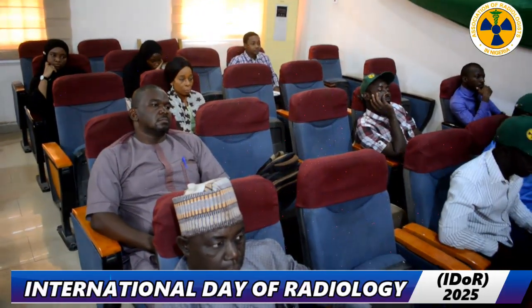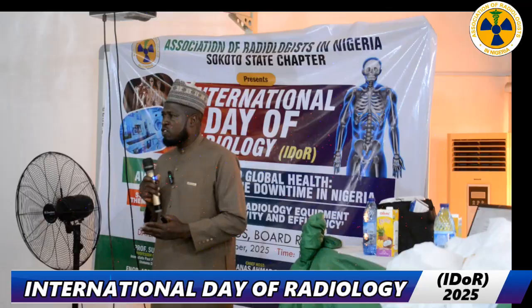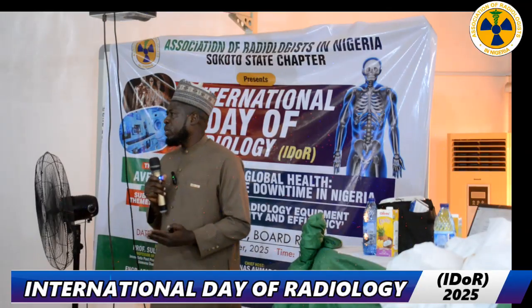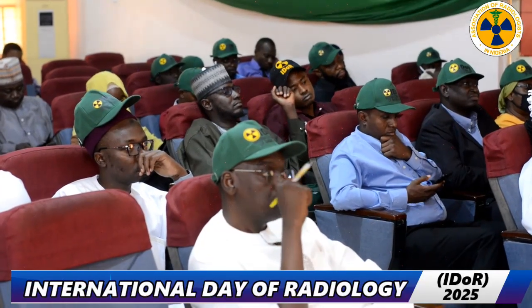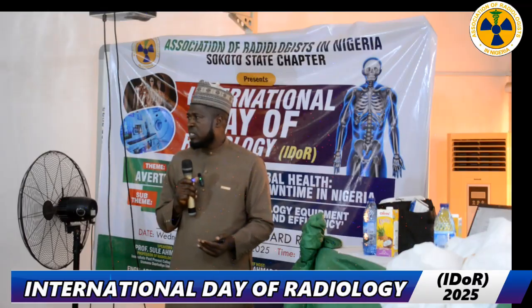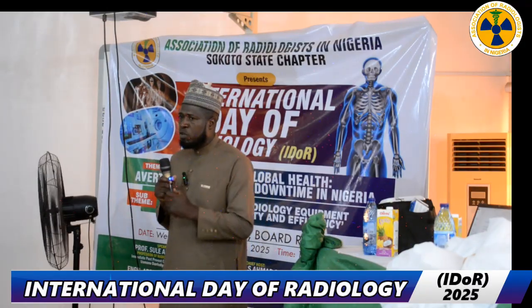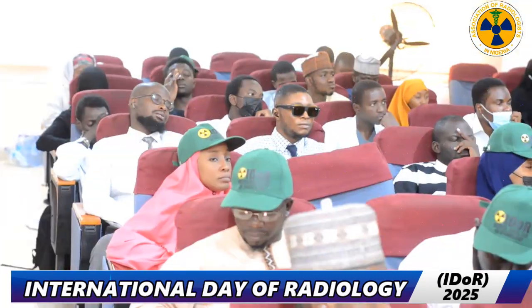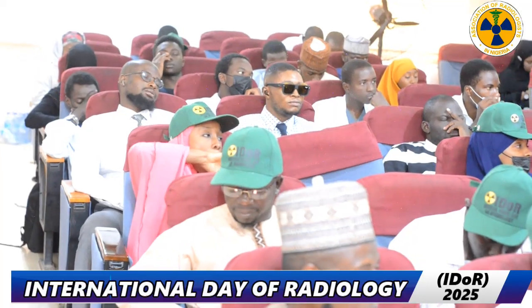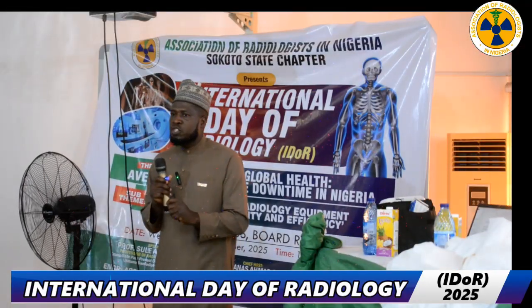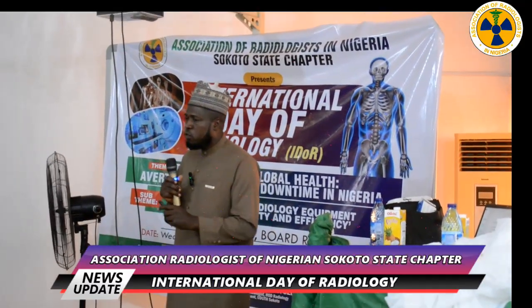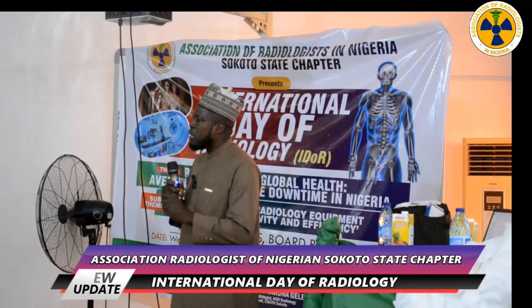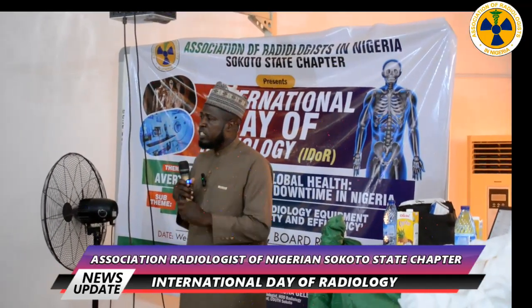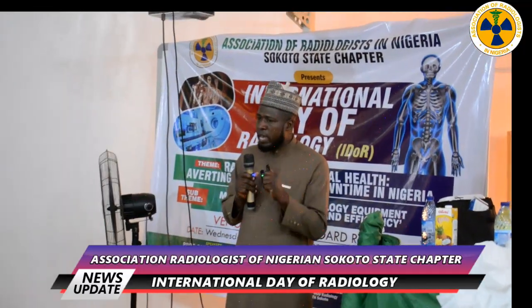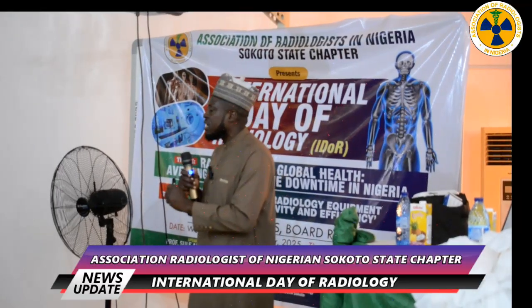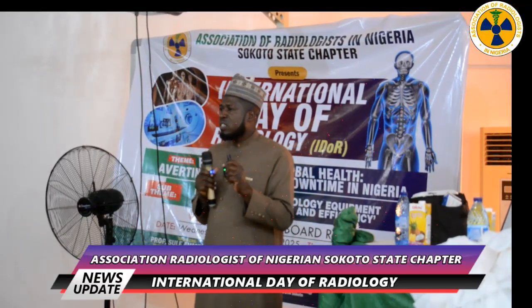Causes of machine failure. What are the causes of machine failure? Some of the causes of machine failure include power surge. What do we mean by power surge? A power surge is a flow of excessive high voltage or current into any medical equipment. When there is a flow of excessive voltage in equipment, it destroys most of the components in the machines. Therefore, there is need for us to provide protective devices such as a UPS, stabilizer or an automatic voltage regulator, which are very useful in terms of maintenance of any medical equipment. In developing countries now, no facility will be installed without having this protective device.